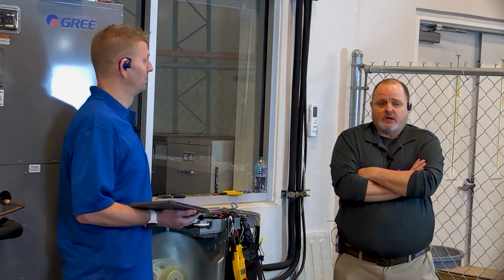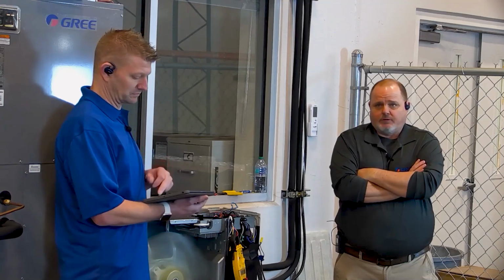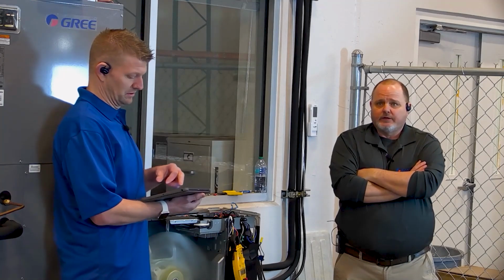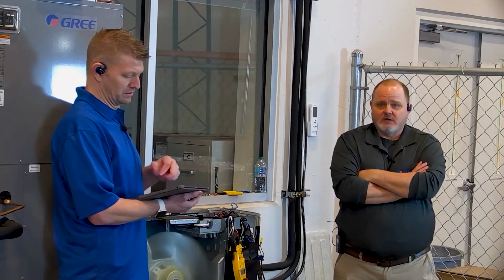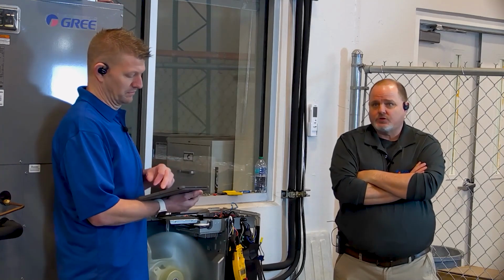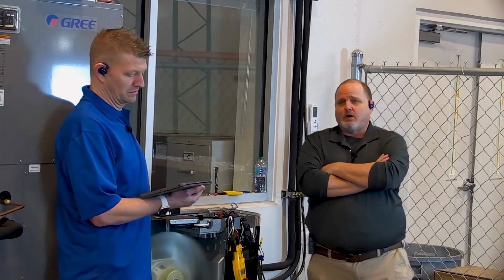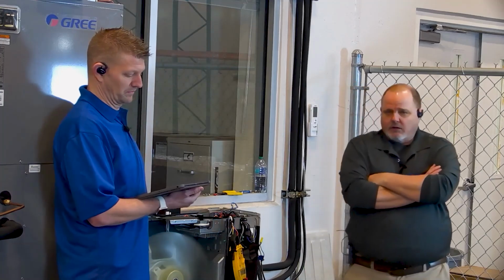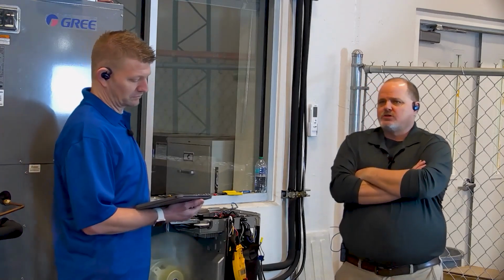But we stress that all the time, and I'm glad he's paying attention. I guess he's looked at our error code tool. That's one of the first things we tell him to do, hook up the gauges and see if the pressure is equivalent to your outdoor temperature, because it should be. If it hasn't been running for quite a while, then you'll know, that could be a dead giveaway. If your pressure is supposed to be 150 pounds, you hook gauges up on both sides and you've got 25 PSI, more than likely that thing is out of gas or near out of gas, right?